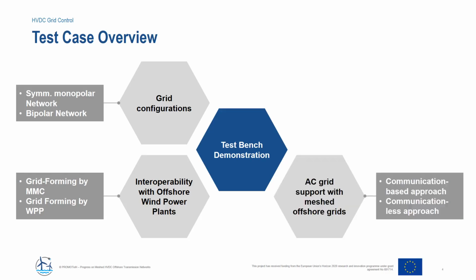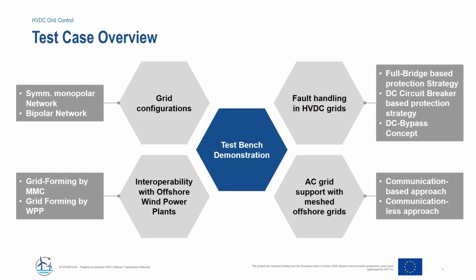Another aspect was the demonstration of the frequency support functions to AC transmission networks using, on the one hand, a communication-based approach, but also using a communication-less approach. Last but not least, we demonstrated different HVDC grid protection strategies. These were developed in our technical work package 4, and they include, on the one hand, a DC circuit breaker based strategy, a DC bypass concept, and the protection of HVDC grids based on fault blocking converters and low voltage and low energy DC circuit breakers.